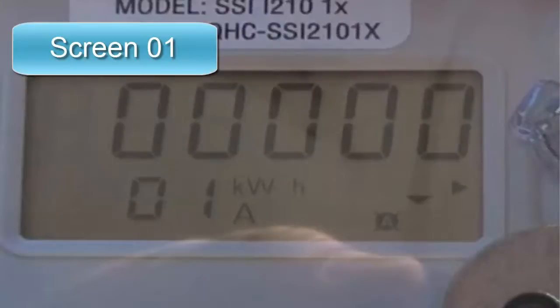Screen 01 should read the kWh as the system remains on. In order to validate correct installation, make sure that the read direction is left to right. This can be confirmed by looking at the direction arrow and watching the direction ticker.